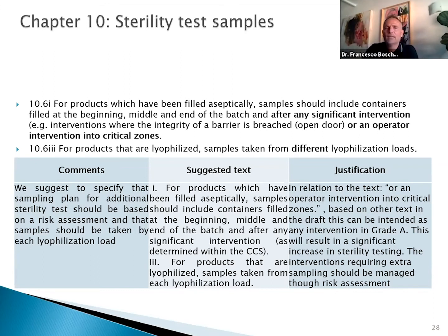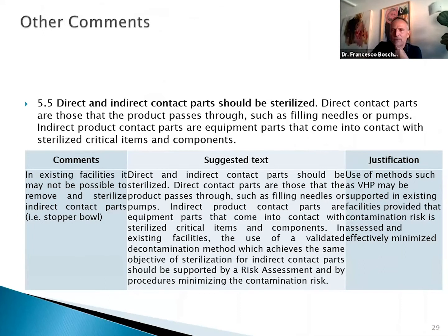Also in point 10.6.3, we have that for products that are lyophilized, samples are taken from different lyophilization loads. We think this word "different" is a little bit ambiguous, so we recommend specifying that samples should be taken from each lyophilization load. Also to harmonize the requirement with the terminally sterilized product, where samples should be collected from each autoclave load. And finally, we have a few comments on the other chapters.